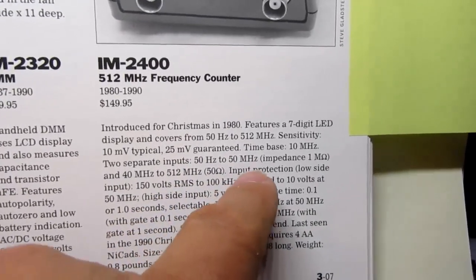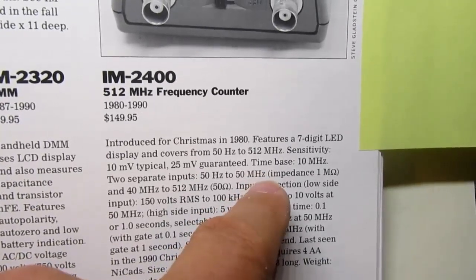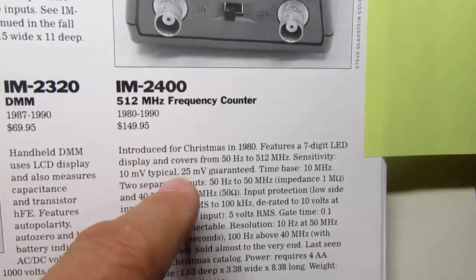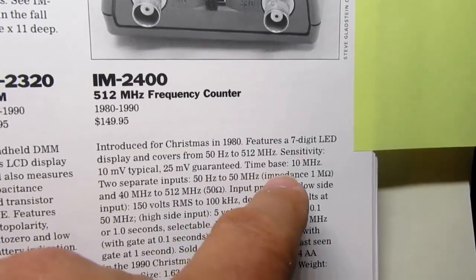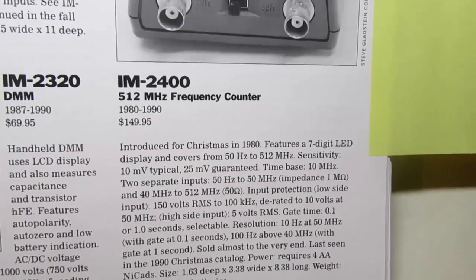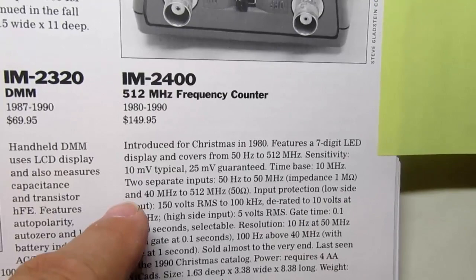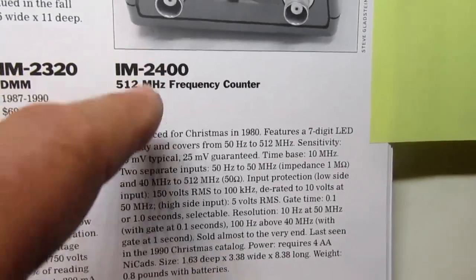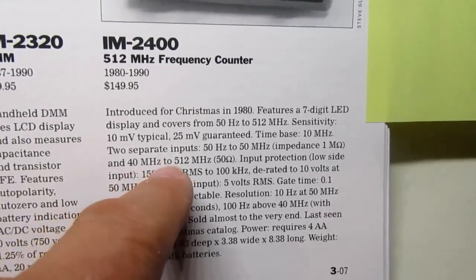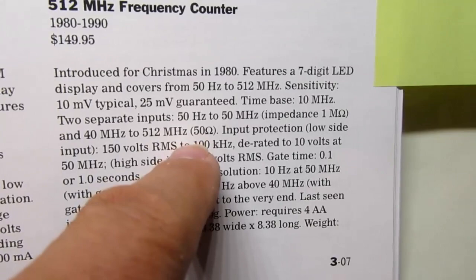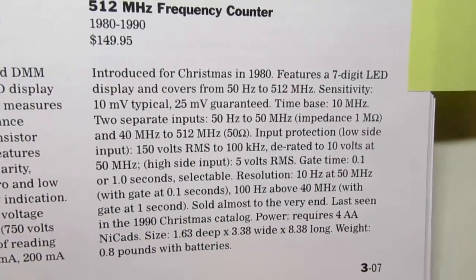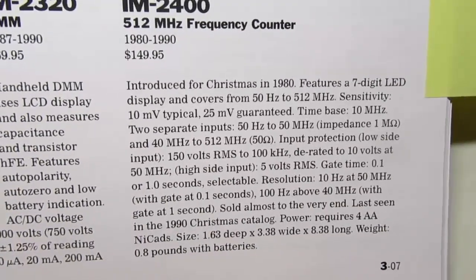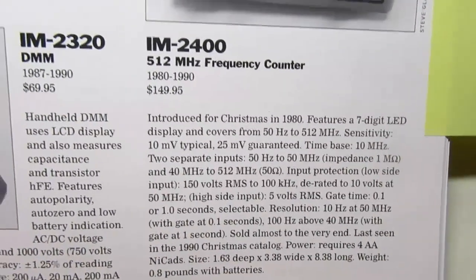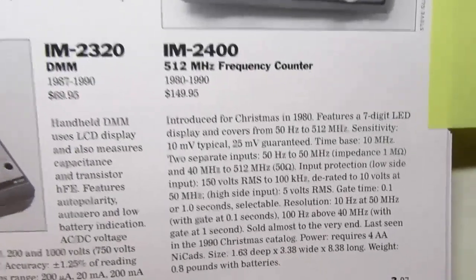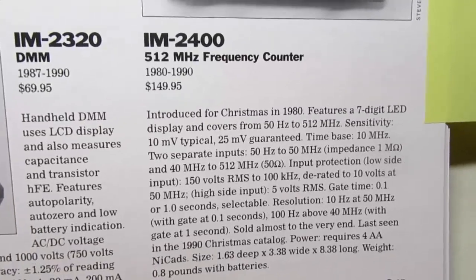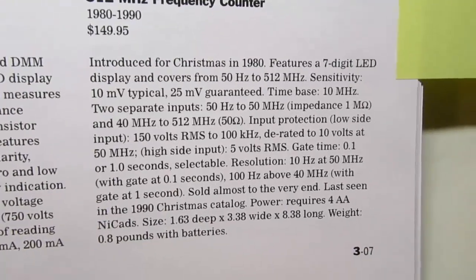Indeed, they recommend that while you can use just a simple BNC connector pair of test leads on the higher impedance input, you're really recommended to use a 10 megaohm times 10 oscilloscope probe on that. That's the best all-around type of cable for that particular input. And then on the higher frequency one, you really need to use something that's designed for 50 ohms, and that can be quite a range of things, of which the manual suggests several options, including just using a simple whip antenna on it, or a simple coil connected up to a BNC connector, and the coil held next to the coil of something in a radio circuit, for example.